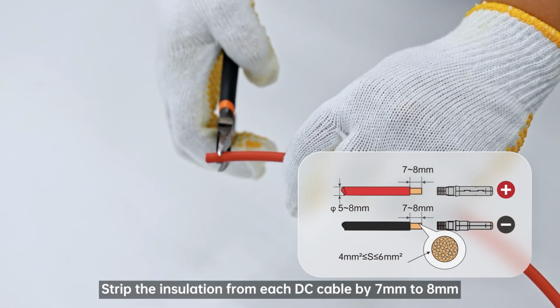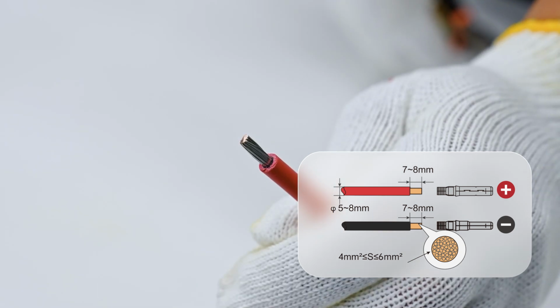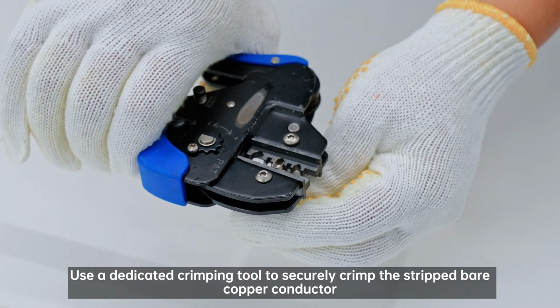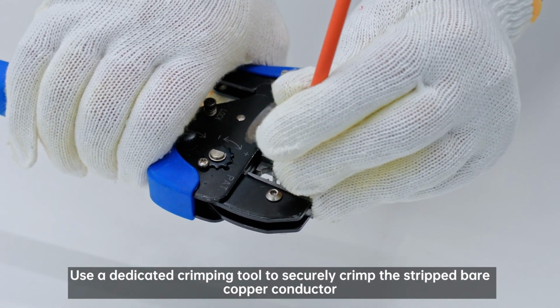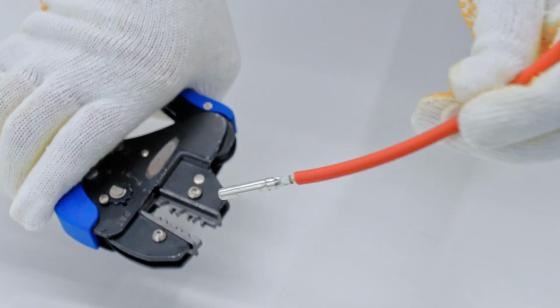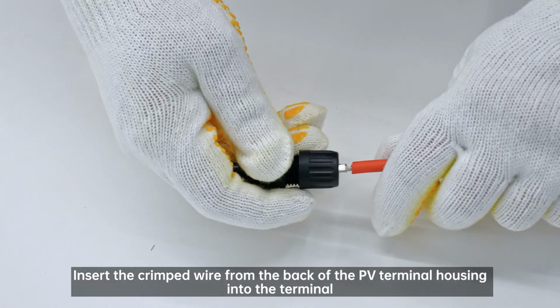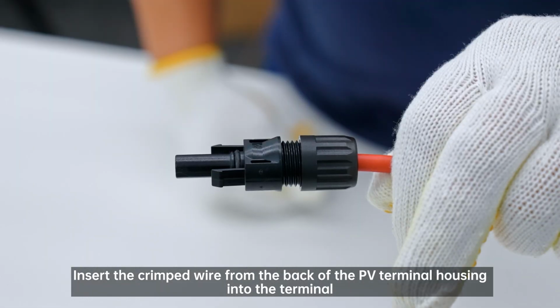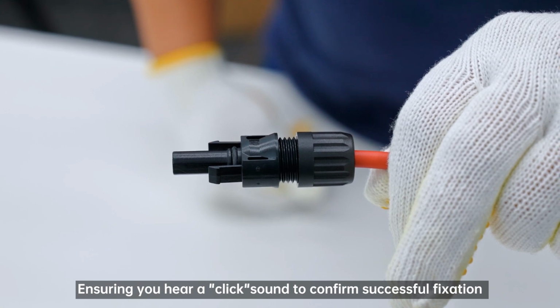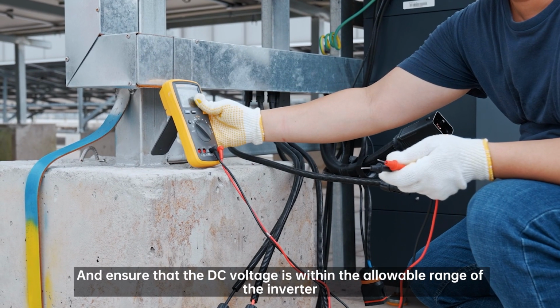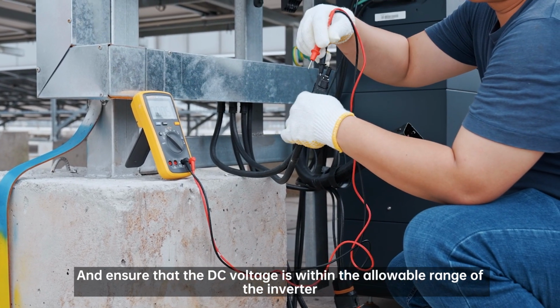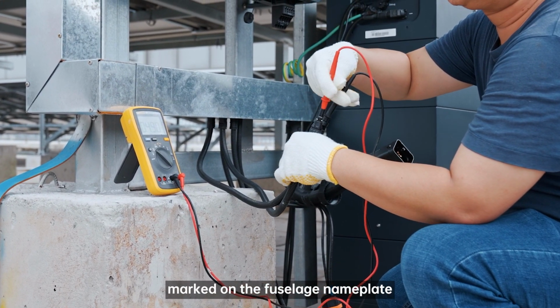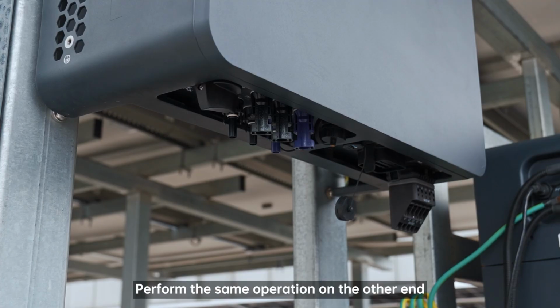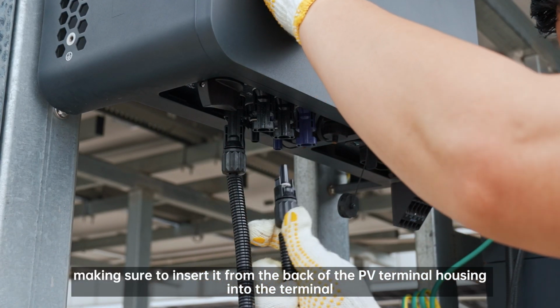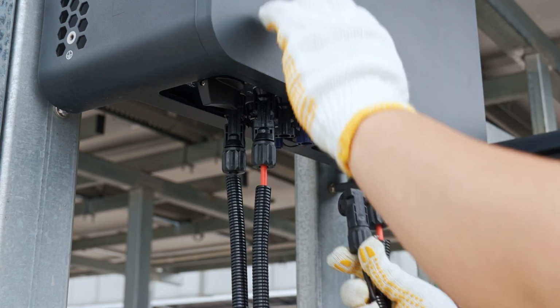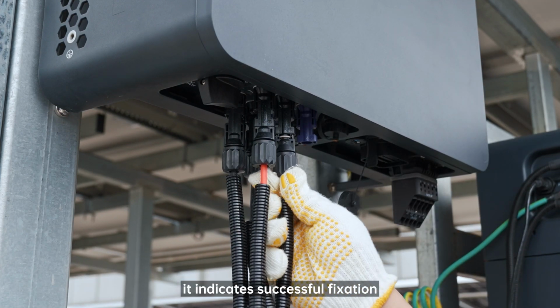Strip the insulation from each DC cable by 7 to 8 millimeters. Use a dedicated crimping tool to securely crimp the stripped bare copper conductor. Insert the crimped wire from the back of the PV terminal housing into the terminal, ensuring you hear a click sound to confirm successful fixation. And ensure that the DC voltage is within the allowable range of the inverter marked on the fuselage nameplate. Perform the same operation on the other end, making sure to insert it from the back of the PV terminal housing into the terminal. Once you hear a click sound, it indicates successful fixation.